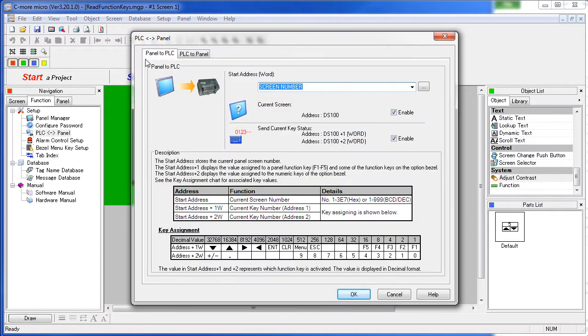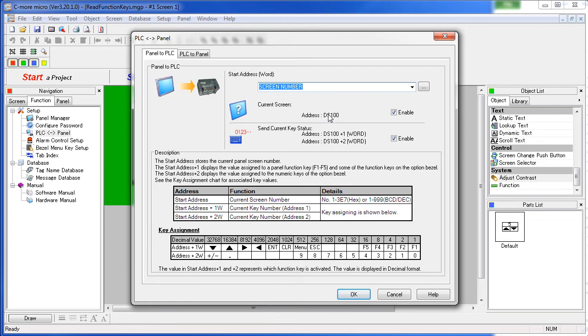Under the Panel to PLC tab, we just enter the PLC tag where we want the panel to send the current screen number – not the function keys, the screen number. We're using the screen number tag, which is located at address DS100 on a click PLC.